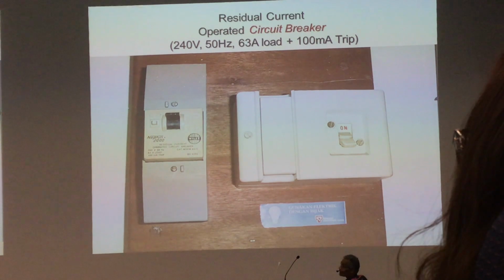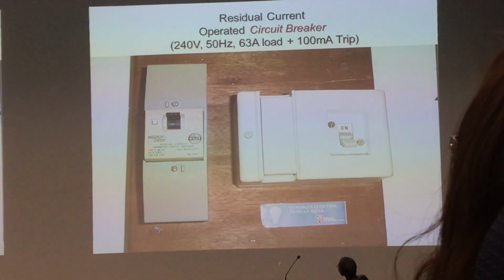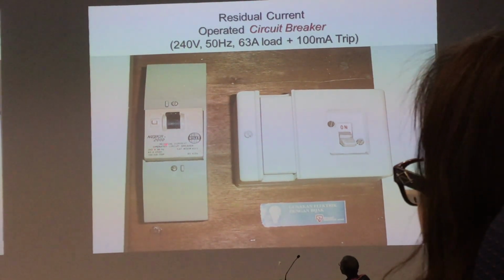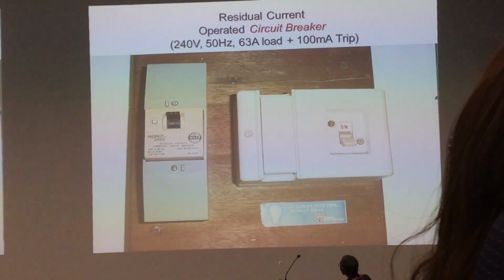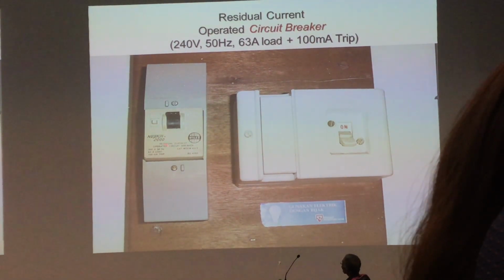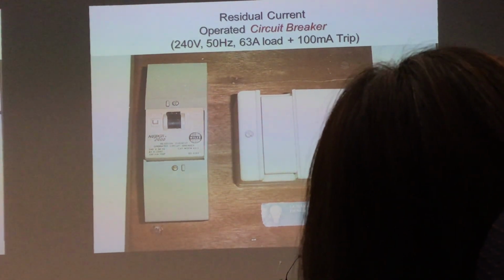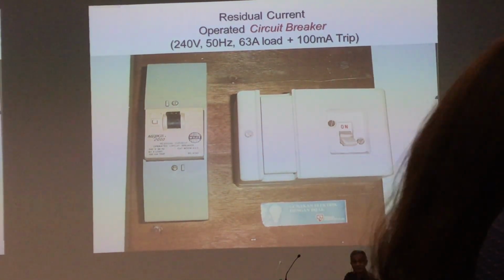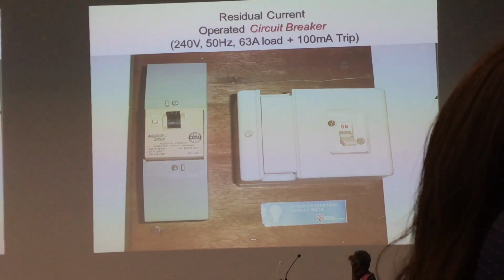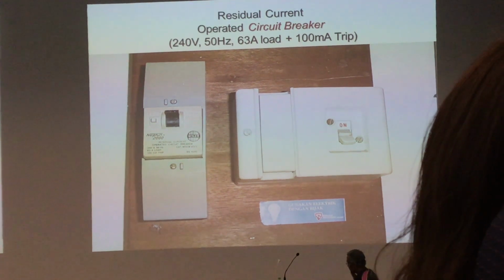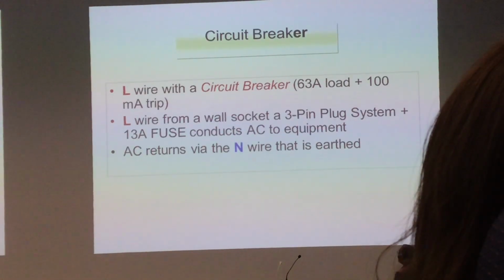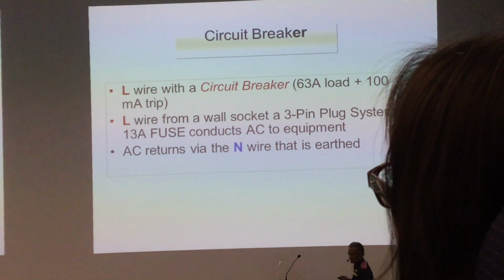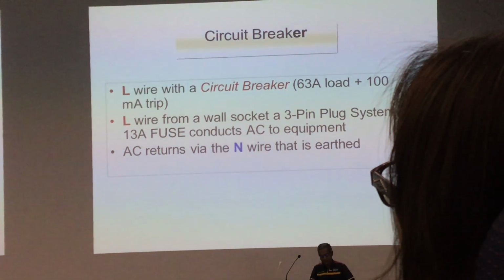70 in, disconnected. Let's say going in 60, going out 58, it trips, because the trip setting there is 100 milliamp, which means there's a current difference. Understand? Going in 60, going out 58, the 2 amp difference will cause a trip, which means disconnected. So that's another safety feature, which means the current going in should be equal to the current going out. If there's a difference, it gets disconnected. Okay? This is an example of a circuit breaker.